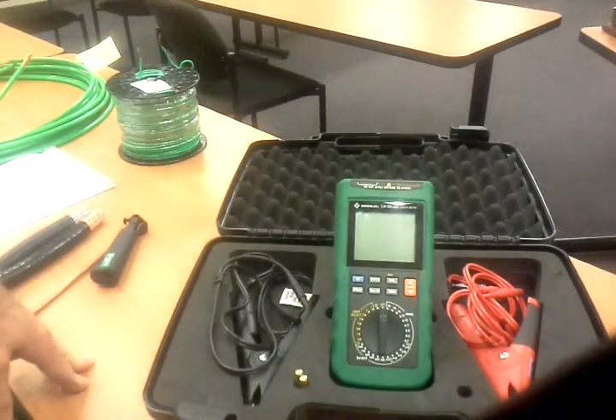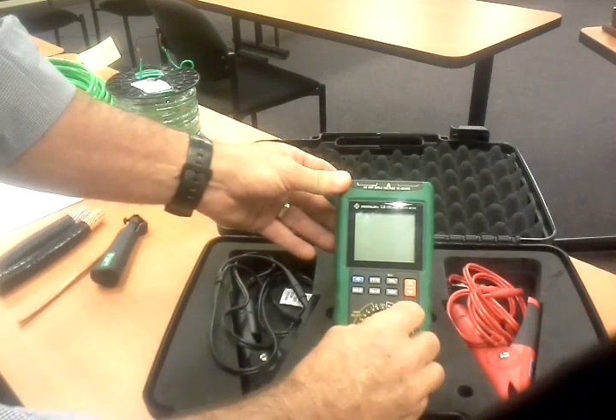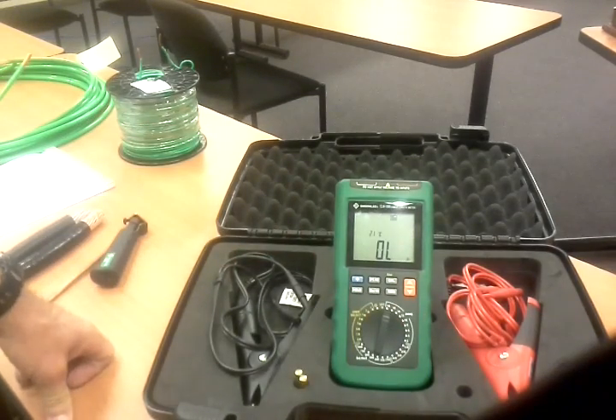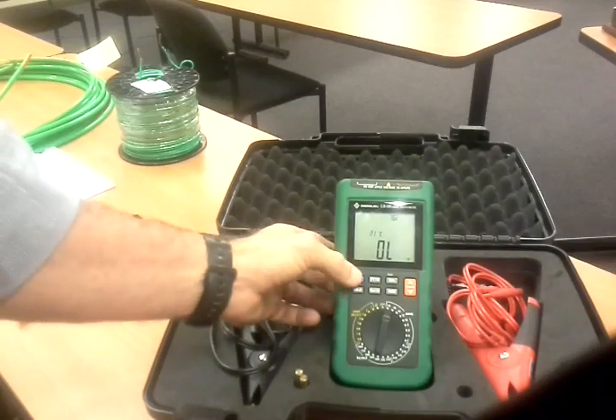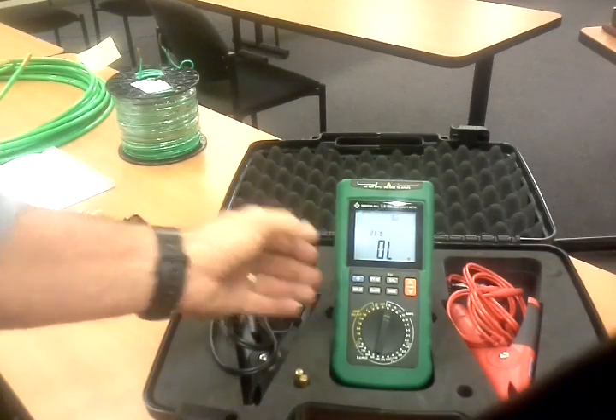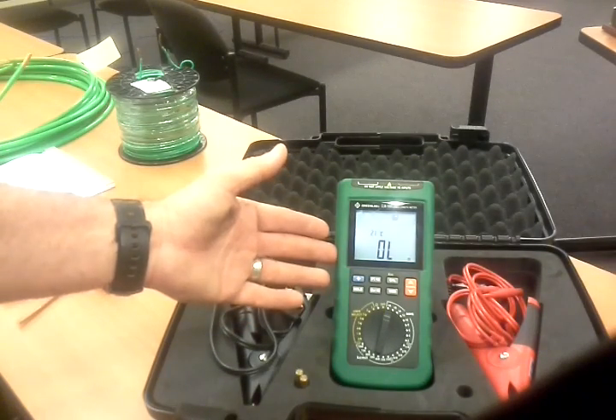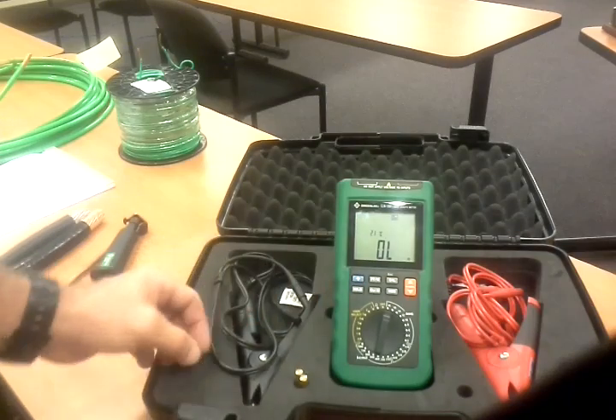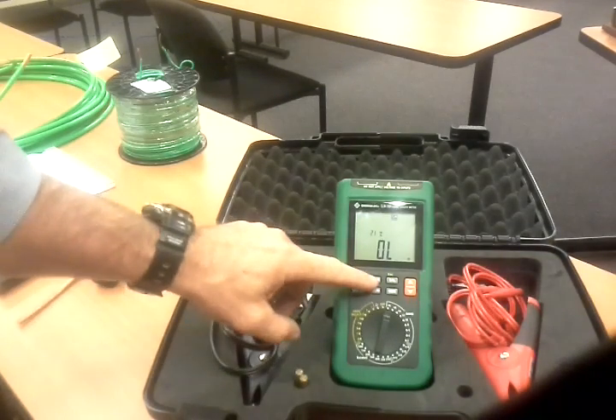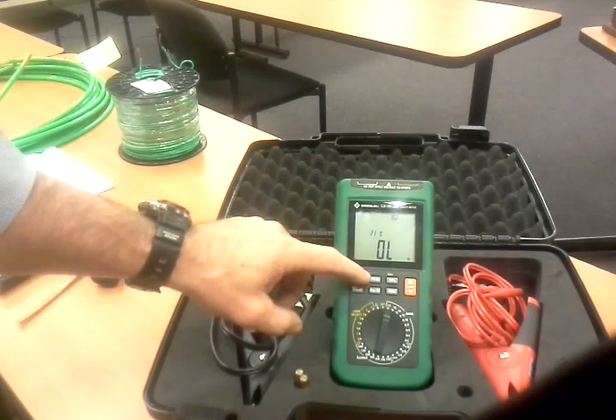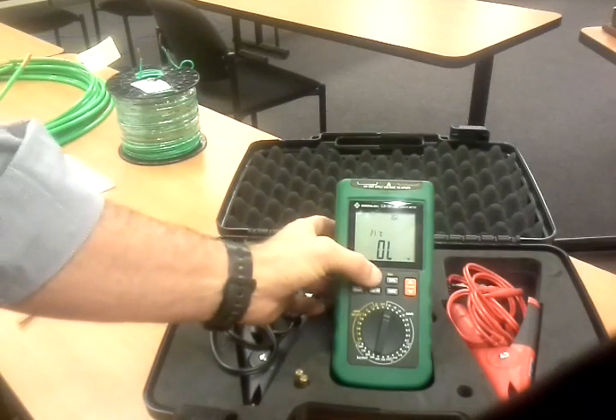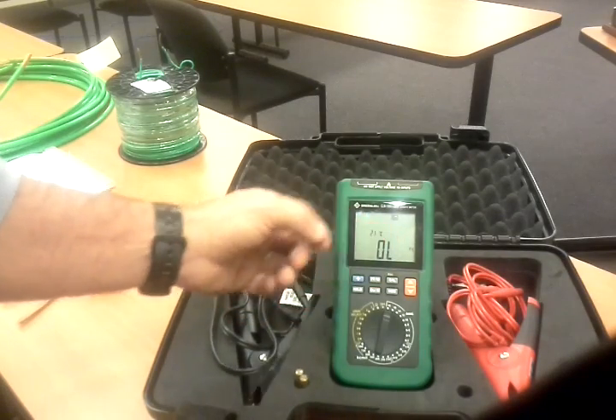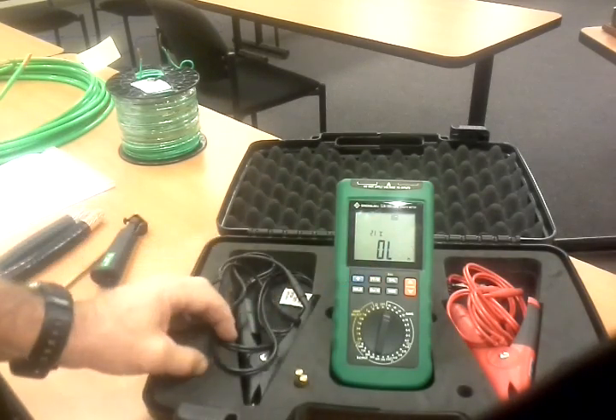To show the operation of the buttons on this meter, we'll go ahead and turn the rotary switch to 18 gauge. You have a backlight. If you press it once, the backlight comes on. After 30 seconds, the backlight will automatically shut off. To turn it off, just press the button again. If you want to read cable in feet and inches or meters, it's showing meters now. To change to feet, press it once, it'll go to feet, back to meters.